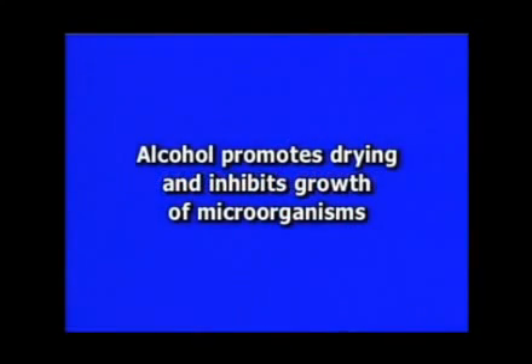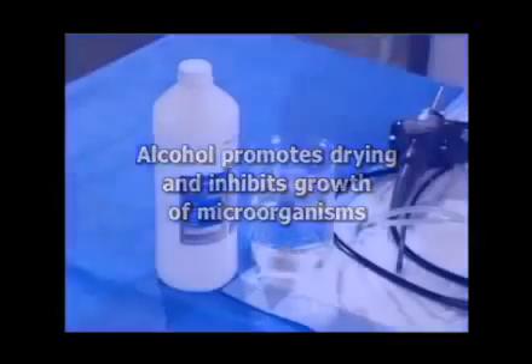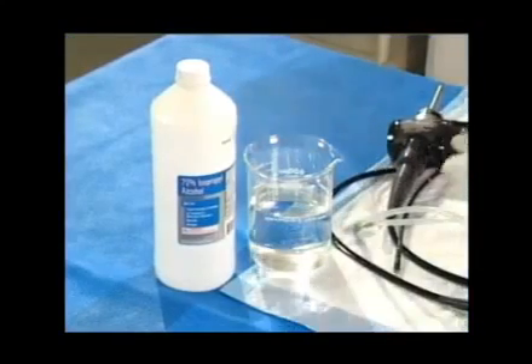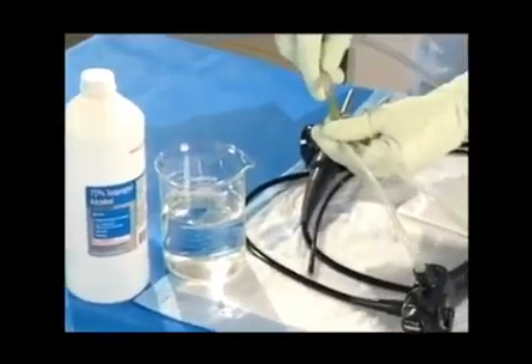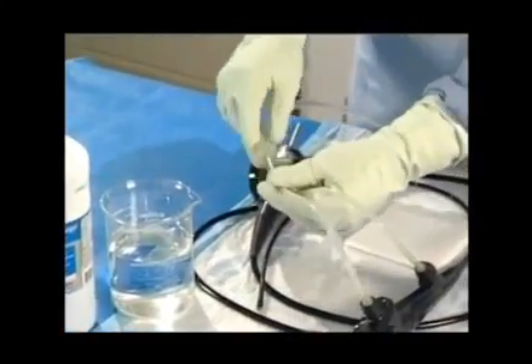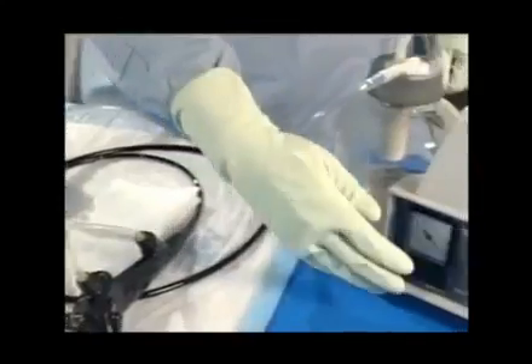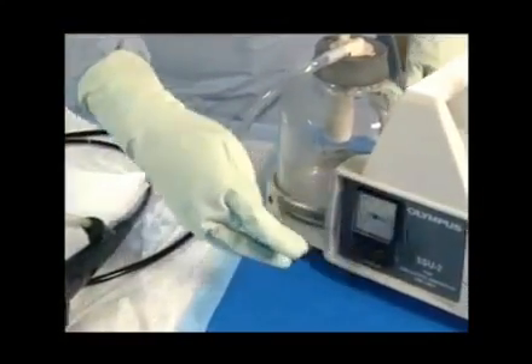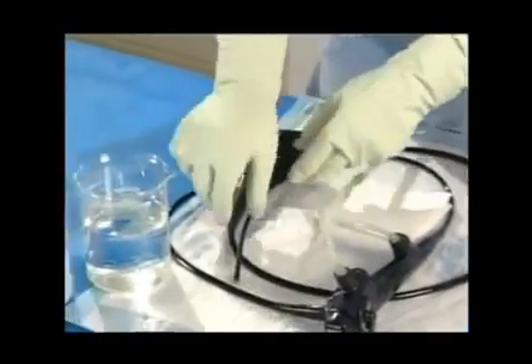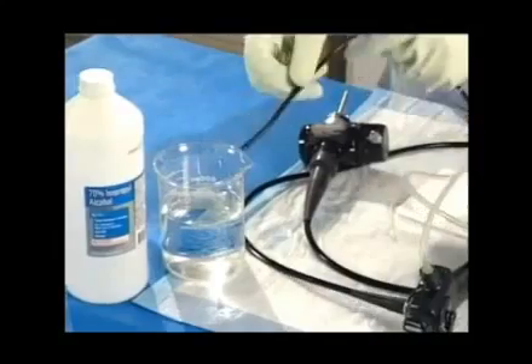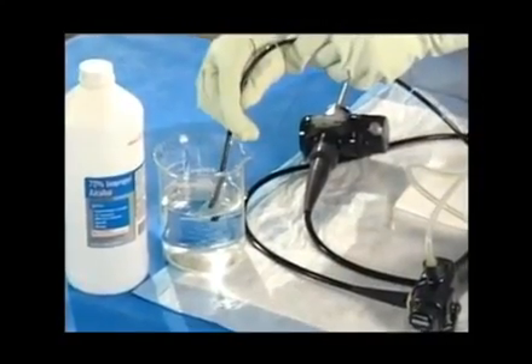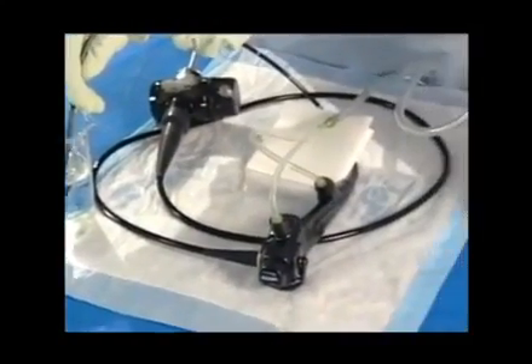The final step in the process is an alcohol flush. Alcohol promotes drying of the endoscope channels and inhibits growth of the waterborne microorganisms. Start by preparing a beaker of 70% ethyl or isopropyl alcohol. Connect the suction cleaning adapter to a source of suction. Immerse the distal end of the bronchoscope in alcohol and aspirate alcohol for 5 seconds.